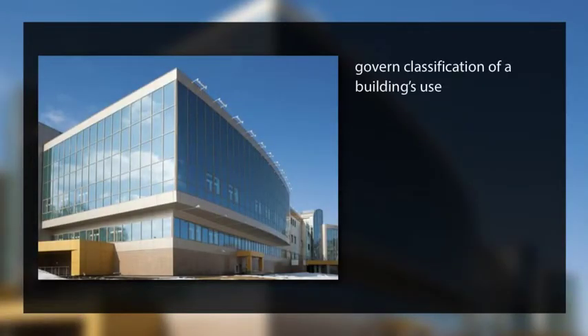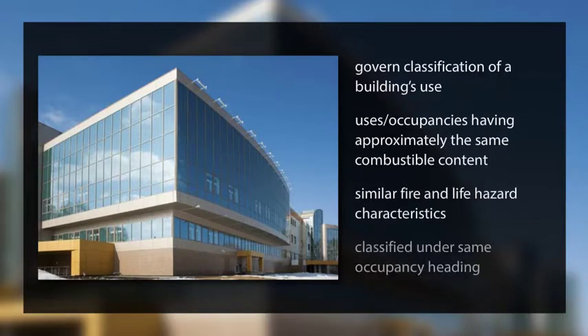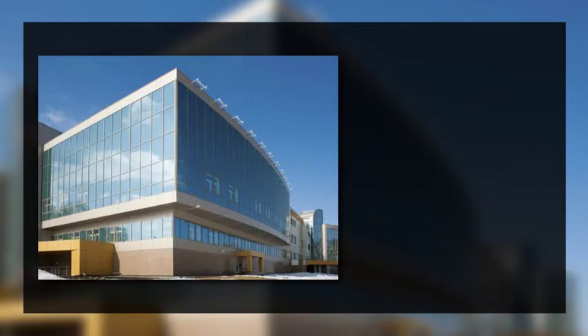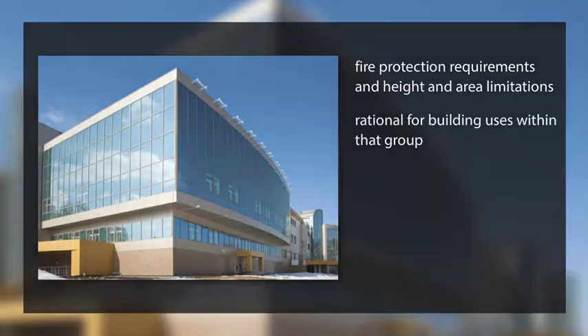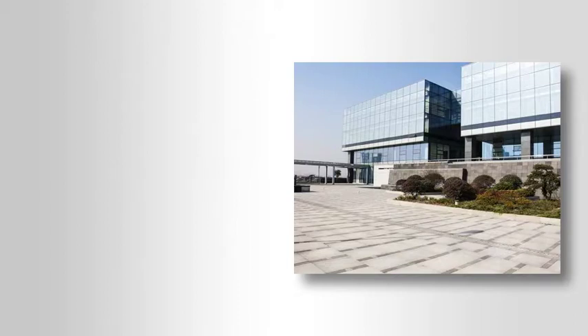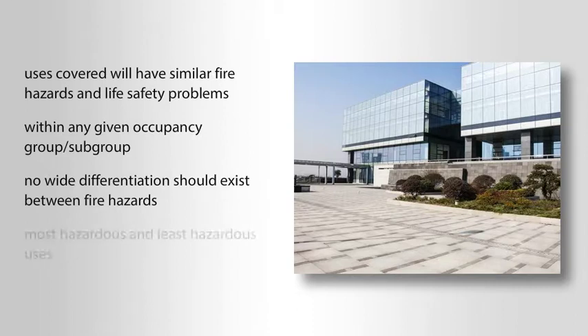The factors that govern the classification of a building's use must be carefully considered so that those uses or occupancies having approximately the same combustible content and similar fire and life hazard characteristics will be classified under the same occupancy heading. Occupancies should be grouped so that fire protection requirements and height and area limitations applicable to the occupancy groups are rational for all building uses within that group. Every classification must be based on the premise that uses covered by each will have similar fire hazards and life safety problems. No wide differentiation should exist between the fire hazards of the most hazardous and the least hazardous uses. The occupancy groups include 10 major classifications.